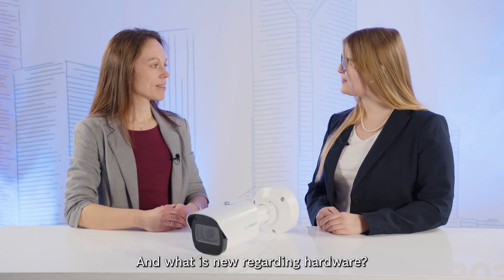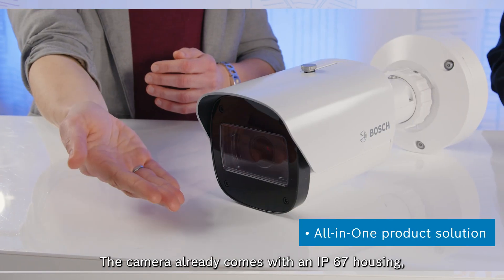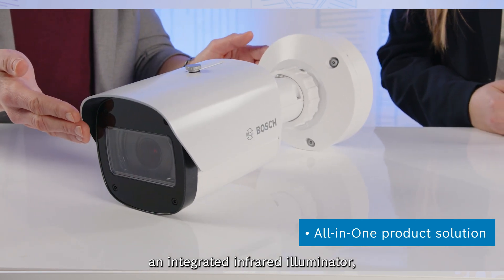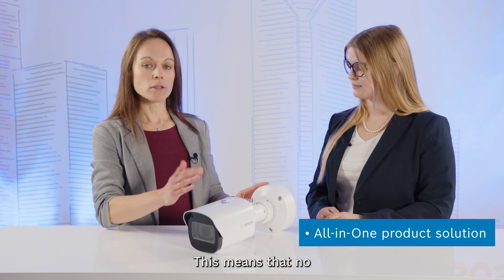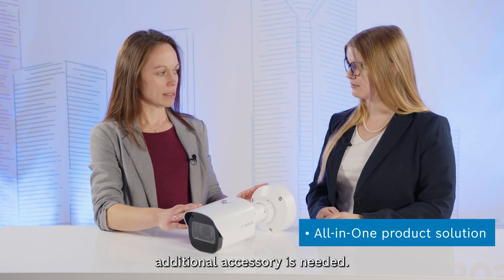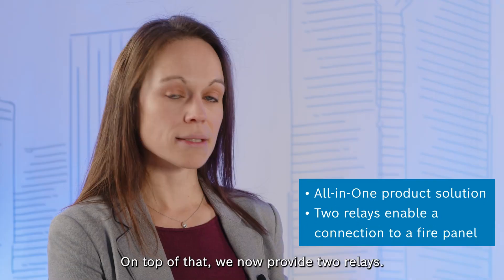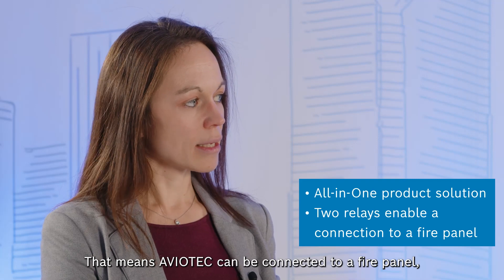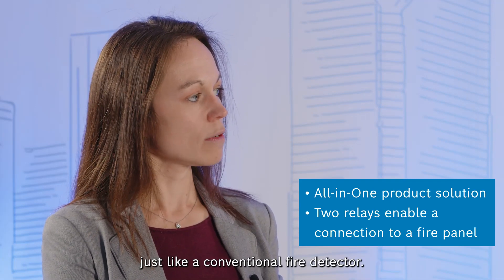And what is new regarding hardware? We now have an all-in-one product solution. The camera already comes with an IP67 housing, an integrated infrared illuminator, as well as a bracket — meaning no additional accessory is needed. On top of that, we now provide two relays: one for alarm, one for trouble. That means AVIOTEC can be connected to a fire panel just like a conventional fire detector.